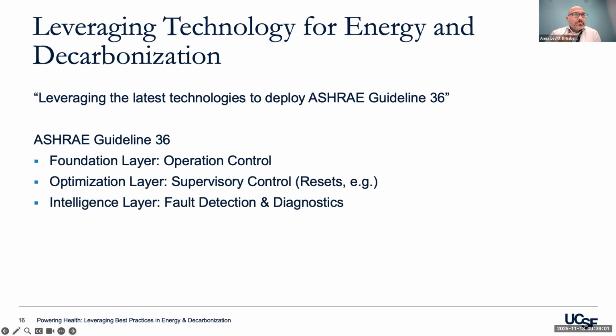It deals with operational controls—how you control air handlers, opening and closing dampers, opening valves. It deals with an optimization layer, the supervisory control, applying resets like temperature and pressure resets. And then the intelligence layer, the fault diagnostic detection.